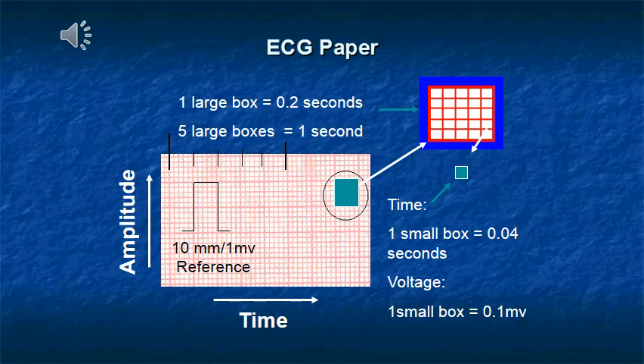The standard calibration of the ECG paper: voltage is at 10 mm per millivolt and time is 25 mm per second. Each small box, which is 1 mm, equals 0.1 millivolt for voltage, and for time each small box equals 0.04 seconds.